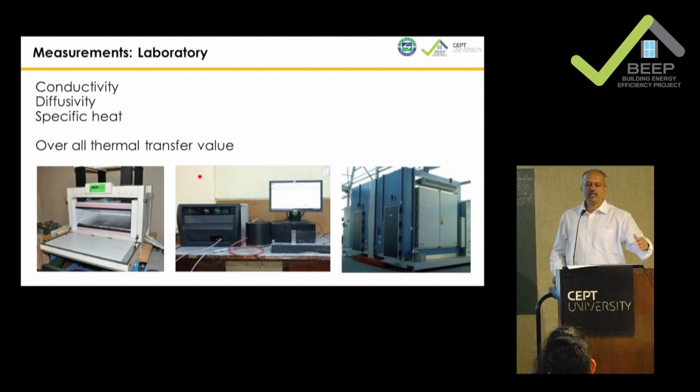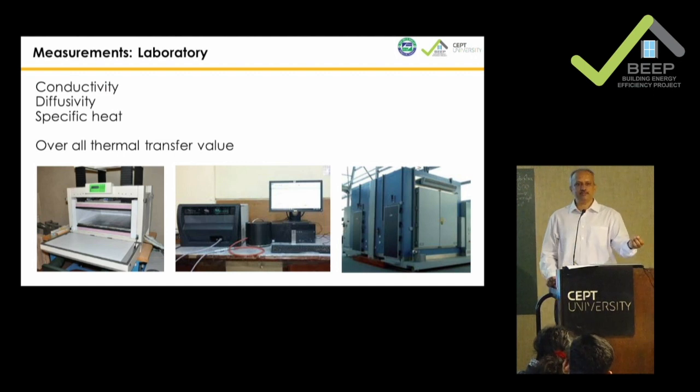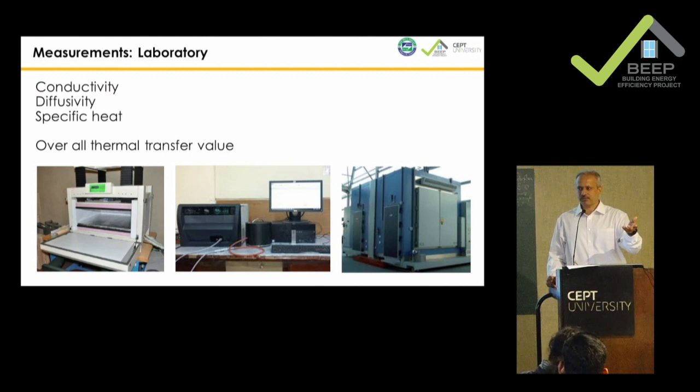The second machine also works with a different kind of material. So this one works on the insulating materials, the other one works for the brick, cement, concrete, the steel, and also the same material in different forms. So you know the cement powder versus cement paste or mortar. The moment you add water, the thermal conductivity will change.